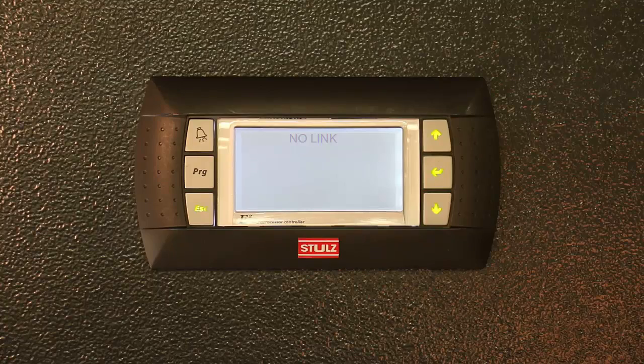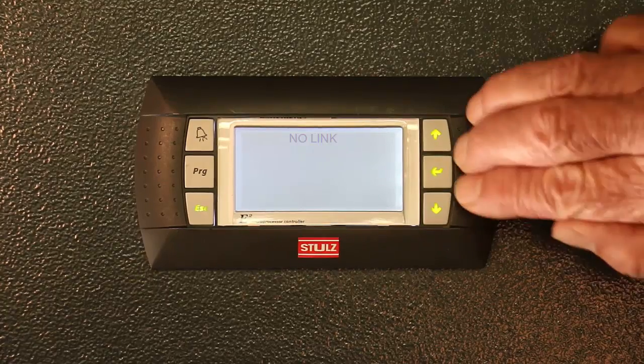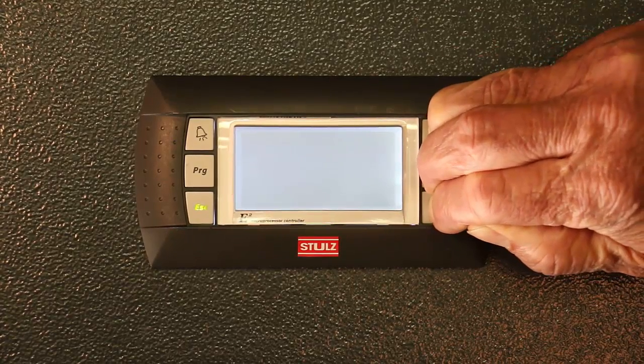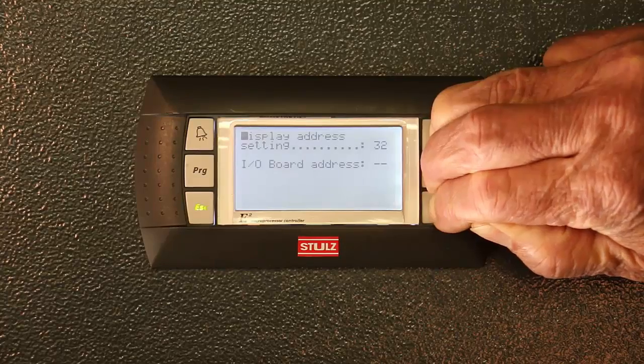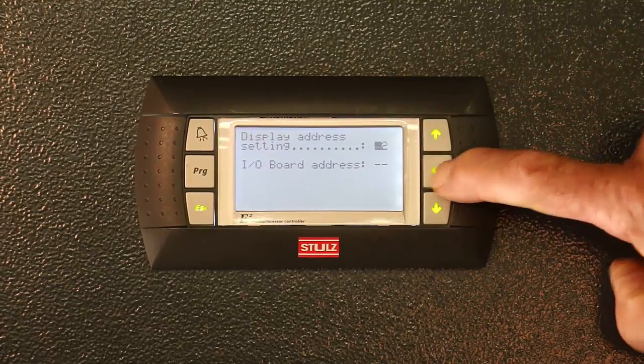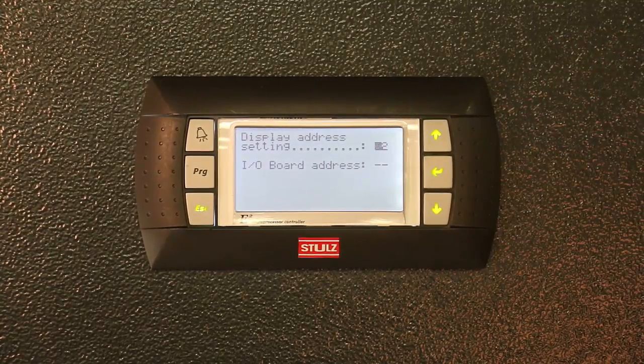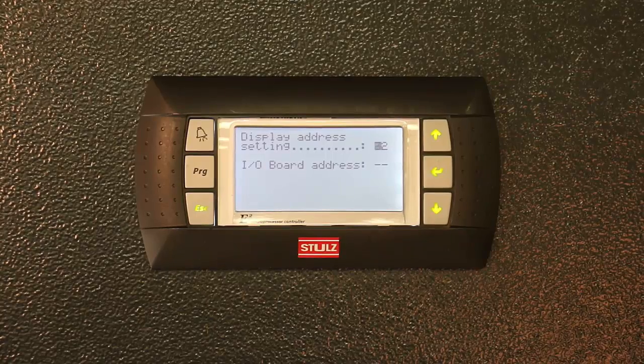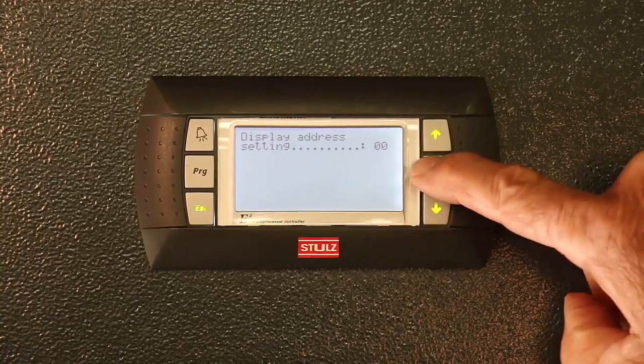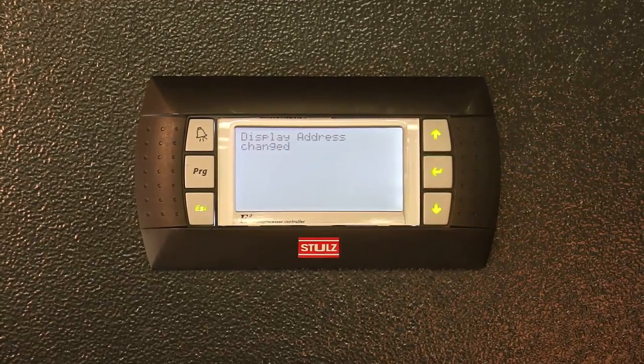We begin by pressing the up, down, and enter keys together. As the address screen appears, press the enter button to move the cursor into the display address number. To change the display address setting, use the up arrow key. Change the number to zero zero, then press enter.